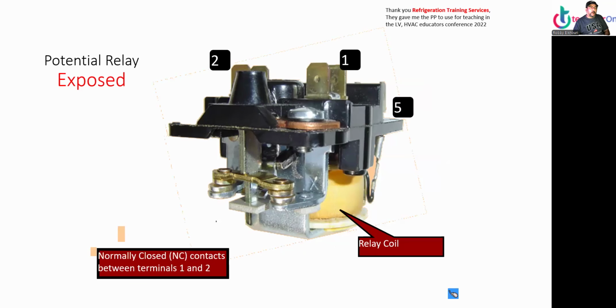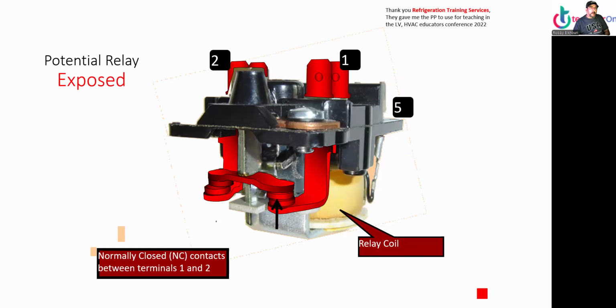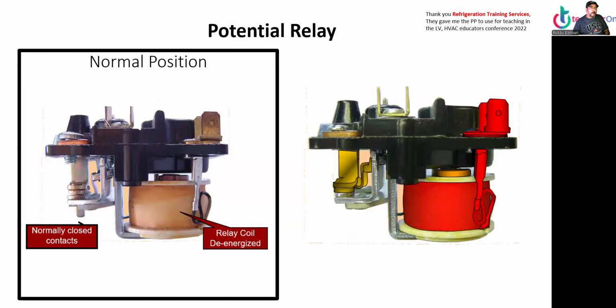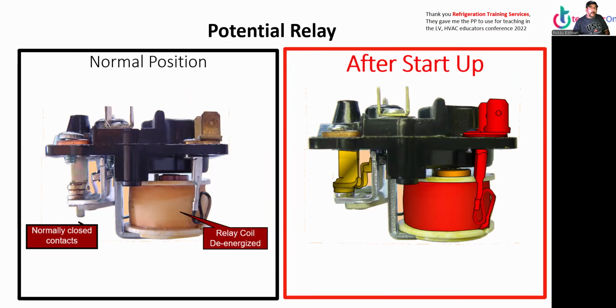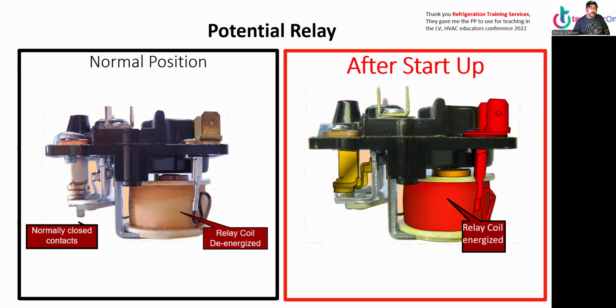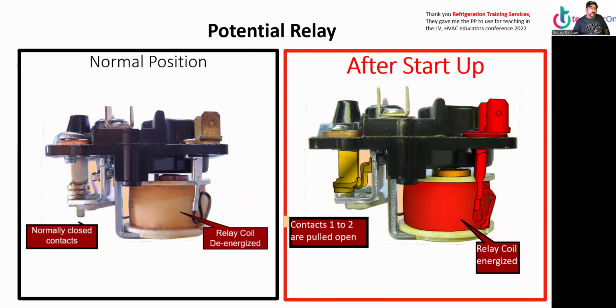There's a relay coil, normally closed, 1 and 2. Closed. Okay, now after startup, coil energized, 1 and 2 are pulled open. That's the difference, closed and open.